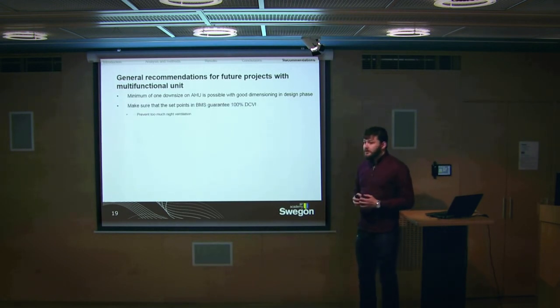It's very important to make sure the building management system guarantees 100% demand controlled ventilation when this equipment is installed. This was not done before, likely because when the building was first used, there was a lot of ventilation to clear emissions from new materials, which is understandable, but someone puts in a number and then forgets to set it to guarantee demand controlled ventilation. That's a shame because this way a lot of energy is used that doesn't have to be.